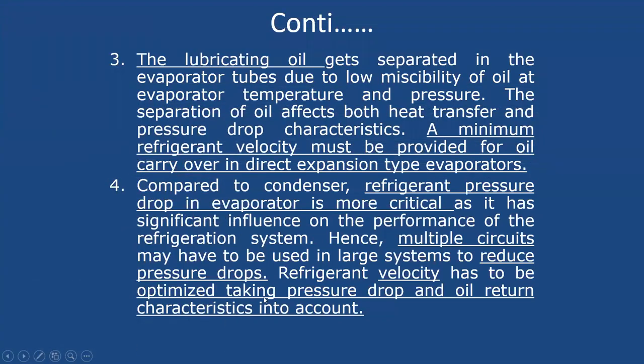the refrigerant velocity has to be optimized, taking pressure drop and oil return characteristics into account. So points 3 and 4 are taken into consideration for maintaining a proper velocity, to minimize pressure drop as well as to maintain oil return characteristics.